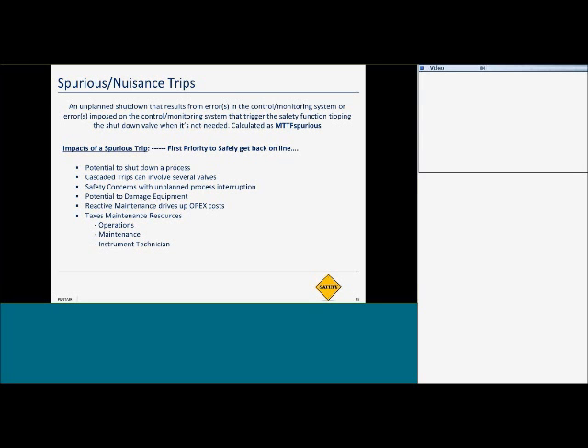Well, why would that be an issue? Well, these are unplanned shutdowns. These are shutdowns that come from false or systematic failures. A lot of times they have to do with the final control element. There's several different issues around that automation package that can cause spurious trips. There's a significant cost to the customers, not just in safety risk, but financially when it comes to spurious trips.